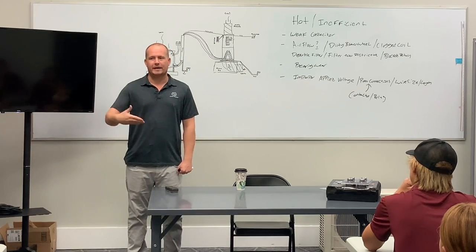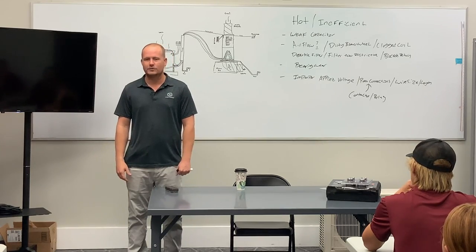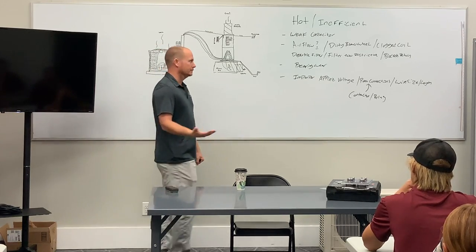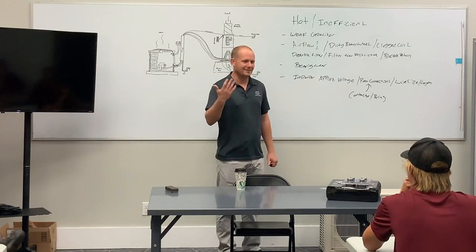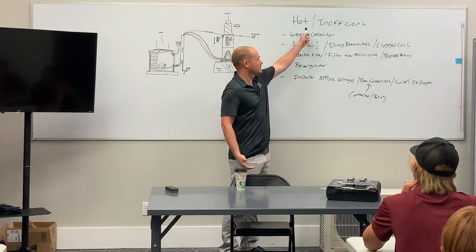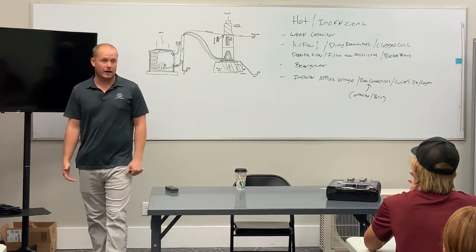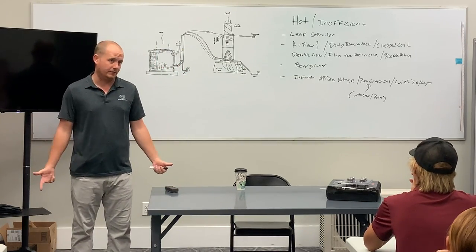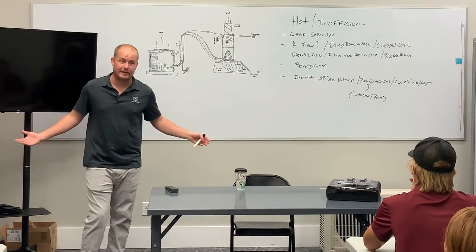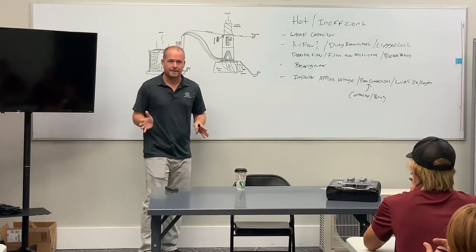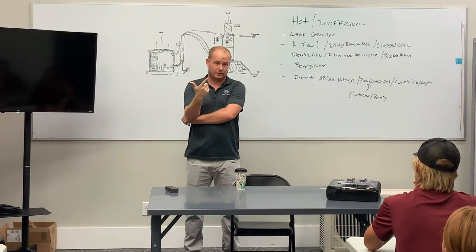We don't replace a weak capacitor because weak capacitors just need replacing, right? We replace weak capacitors, why? This isn't a trick question. We replace weak capacitors because weak capacitors result in hot and inefficient motors, and ultimately, untimely failure of either the motor or the capacitor itself, right? If the capacitor is getting weak, it's also a sign that it's beginning to fail, which can result in them being without air conditioning. Because this is what the customer cares about, right? They care about their unit not drawing too much power and not breaking on them prematurely, right?